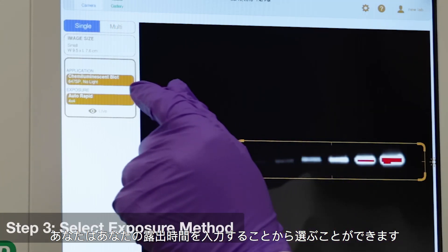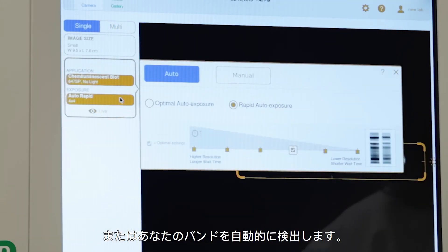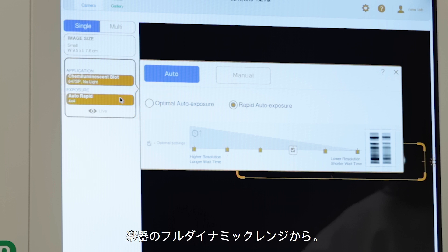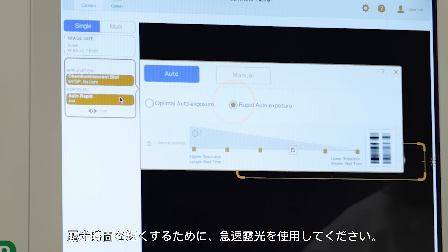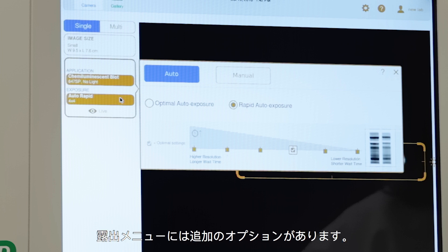You may choose between entering your exposure time or detecting your bands automatically. Use optimal exposure to benefit from the full dynamic range of the instrument. Use rapid exposure for shorter exposure times. For low-light quantitative assays like chemiluminescence, additional options are available in the exposure menu.